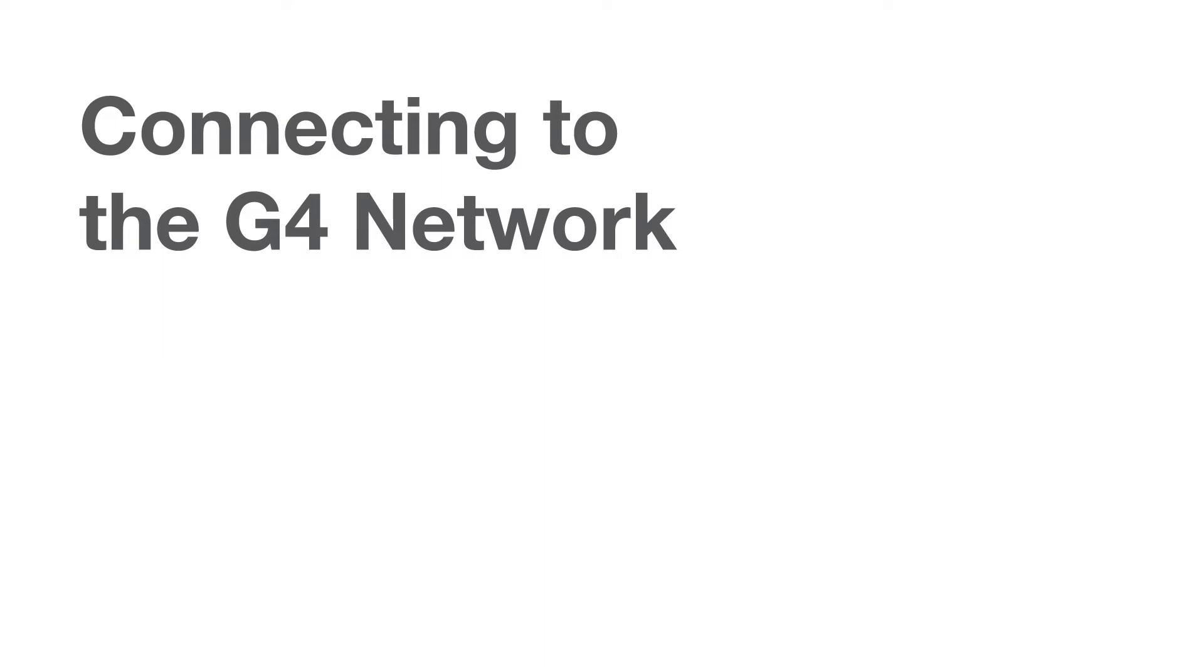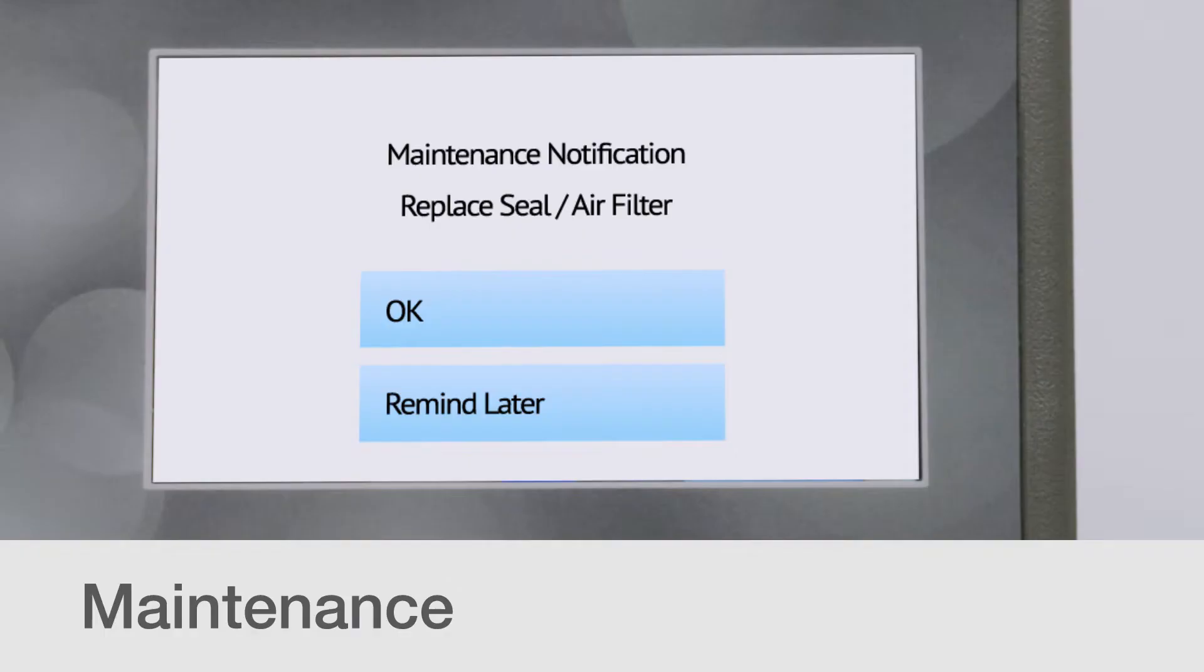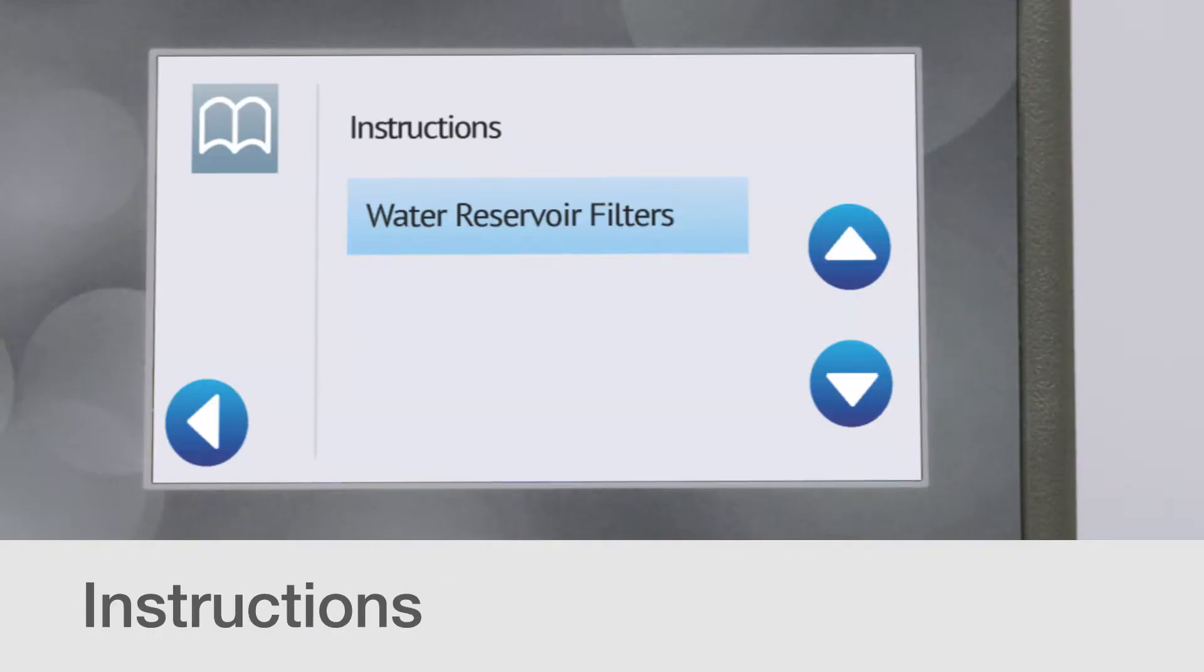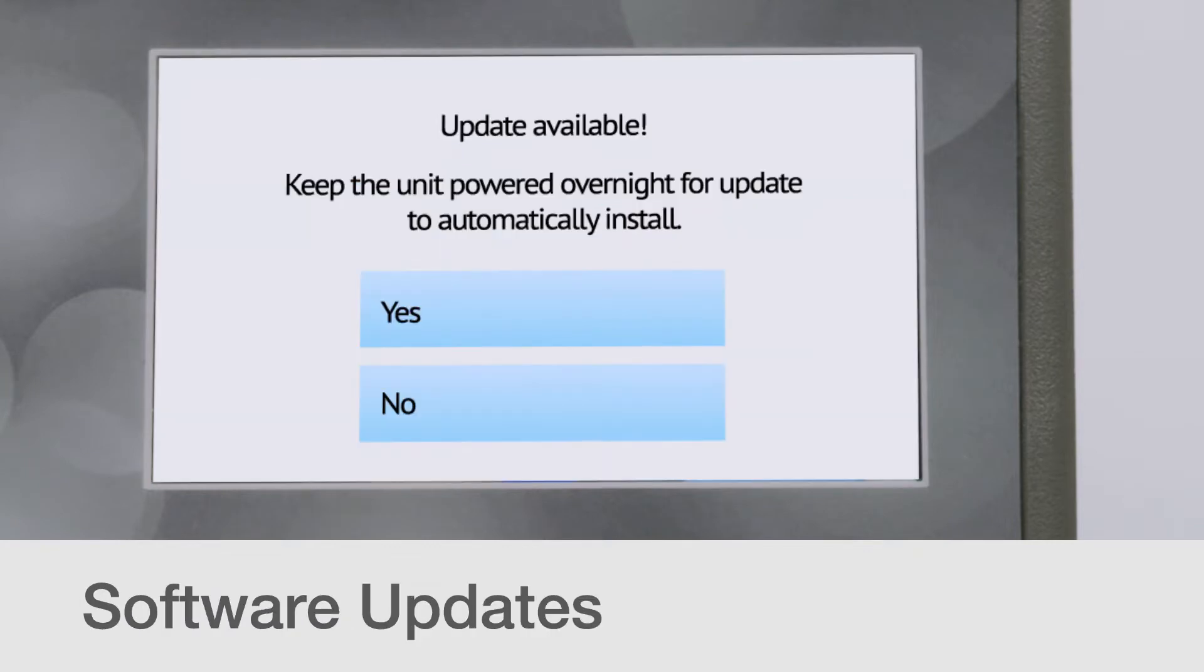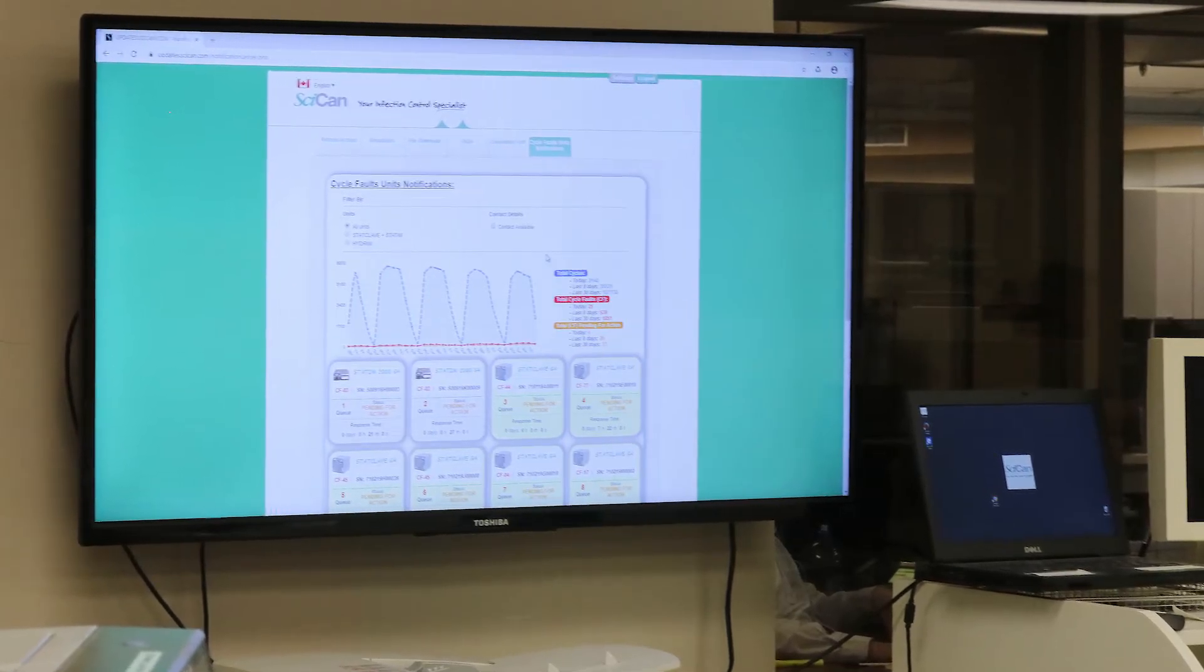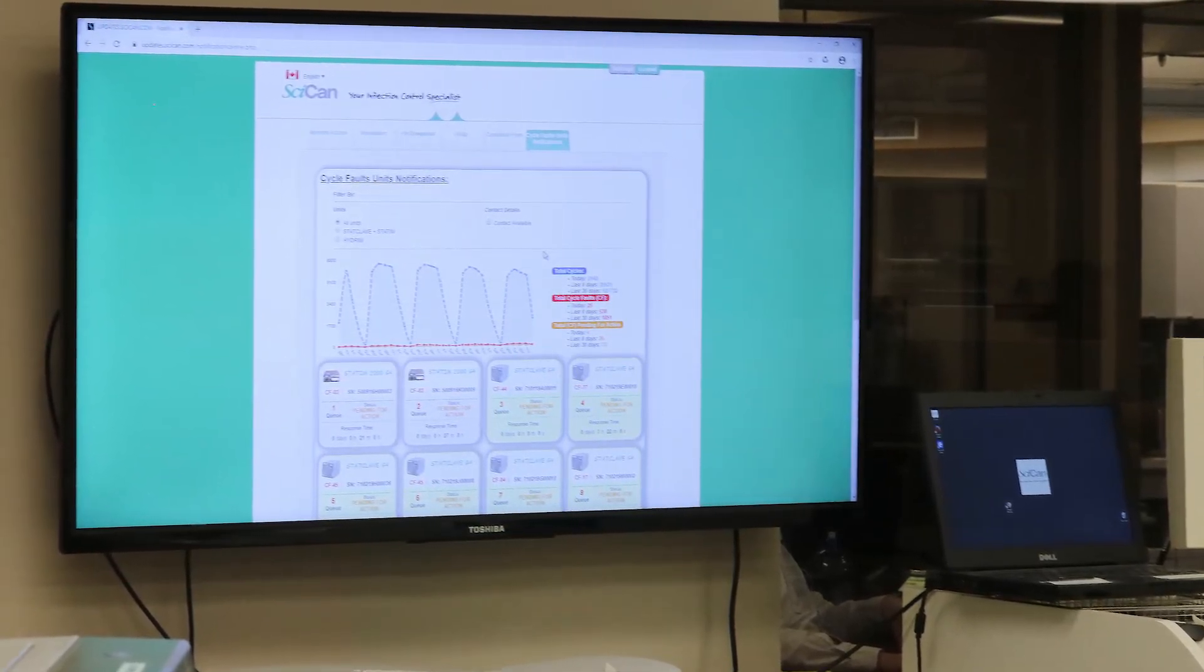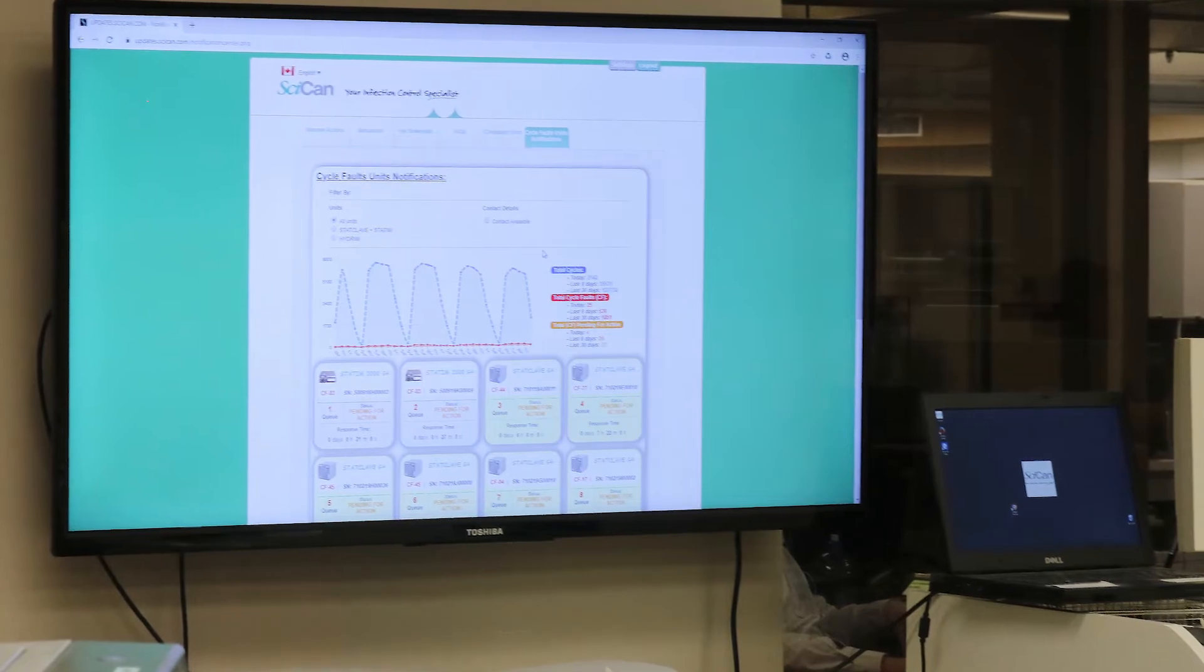StatClave's Wi-Fi enabled G4 technology can connect and send cycle data to your smart devices or computer, allowing staff to focus on the most important thing in a dental practice, the patients. Maintenance reminders, on-screen instructions and the option for automatic user interface software updates are all helpful tools to help keep your StatClave in good working order. Should your machine experience an error, G4 technology connects your unit to specialized technicians, which allows for remote support and minimizes unnecessary downtime.